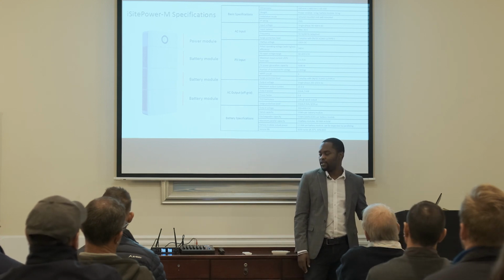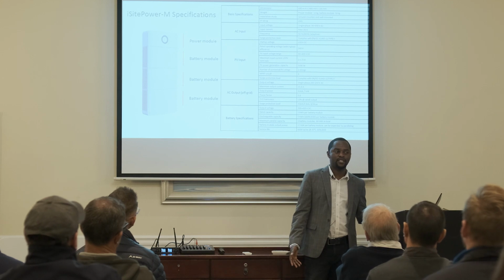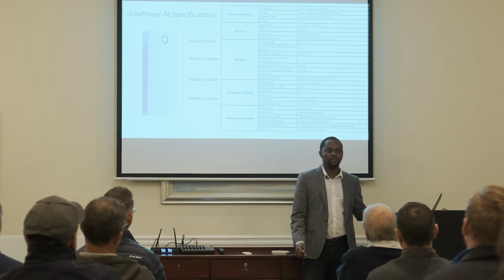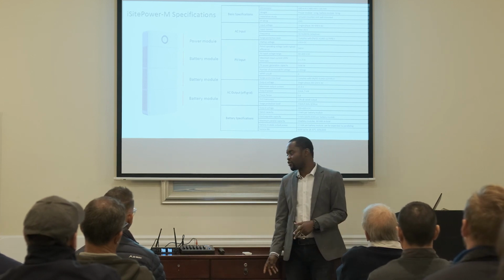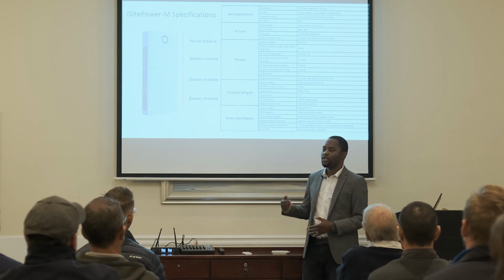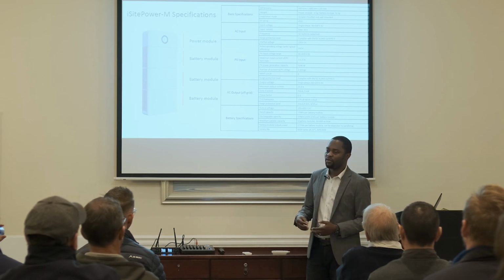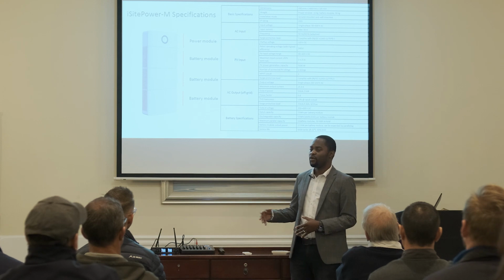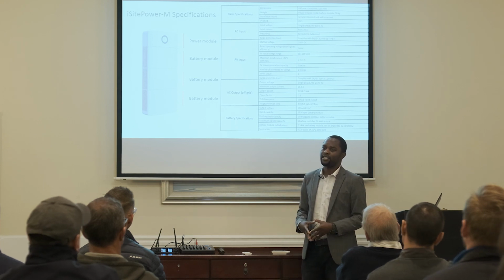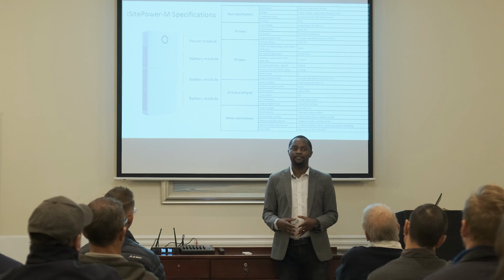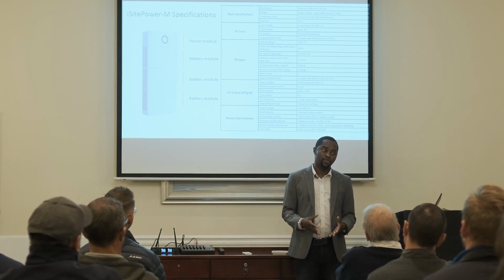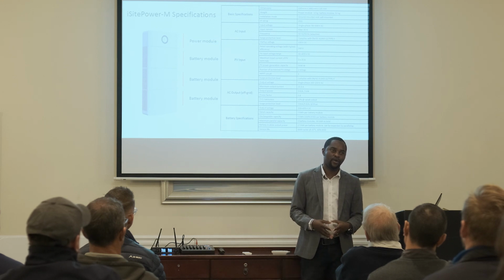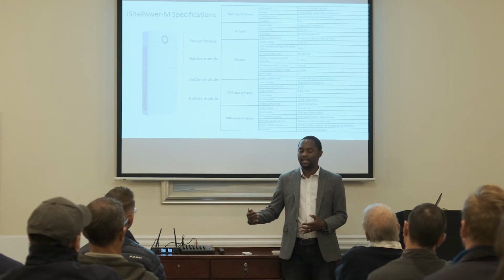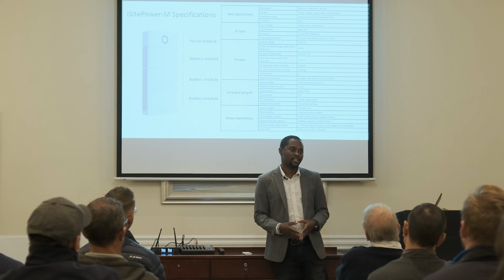Then we would like to define this as a semi-hybrid unit. It's a hybrid because it integrates three different sources of power. You can supply your loads from grid, from your PV, it takes panels, and also from your battery. That makes it a hybrid. But it's a semi-hybrid because you can't feed back to grid. You also can't feed back to non-essentials. So it's UPS based, right? In a way, you can call it a UPS that can take panels. That's why it's a semi-hybrid.